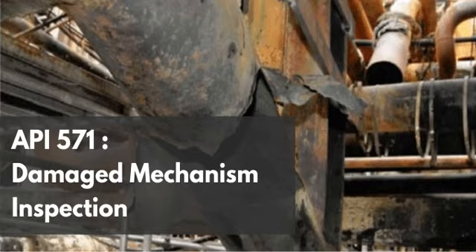Let's dissect this. Why is this specific 0.75-inch tube, this UNS C44300 grade, the poster child for Ammonia SCC? Well, Admiralty brass, like that UNS C44300, is ubiquitous in heat exchangers for a really good reason. I mean, it offers excellent thermal conductivity and generally performs very well against corrosion from typical cooling water. Right. It does its job well normally. Exactly. But its vulnerability to ammonia is its Achilles heel. When you introduce a tube with those specific dimensions and features to an ammonia environment, you're creating a perfect storm.